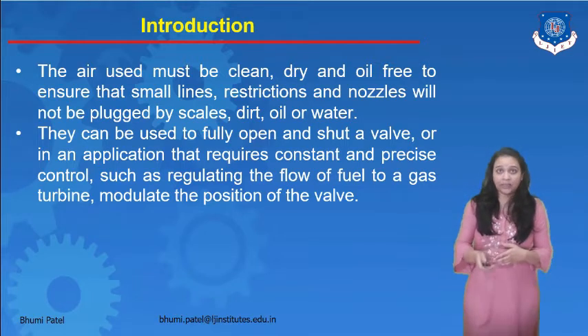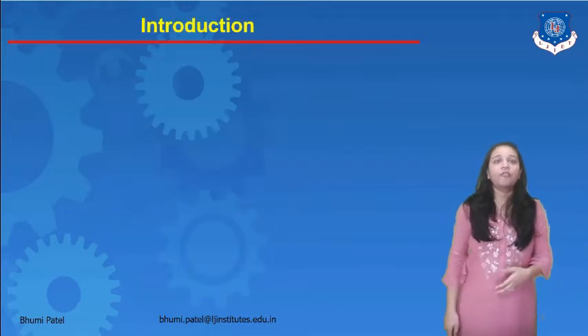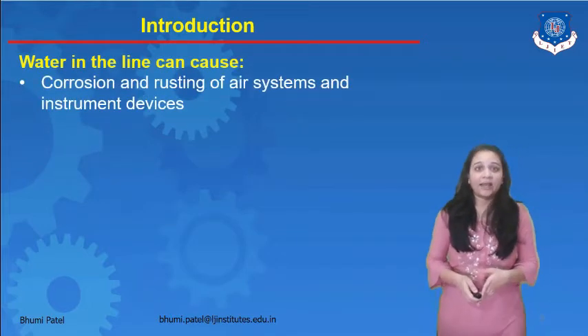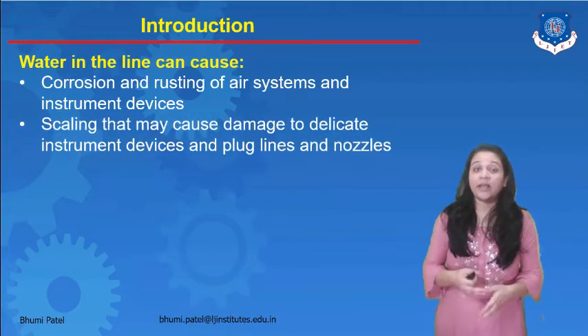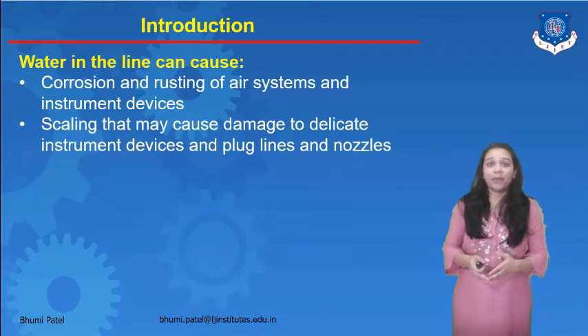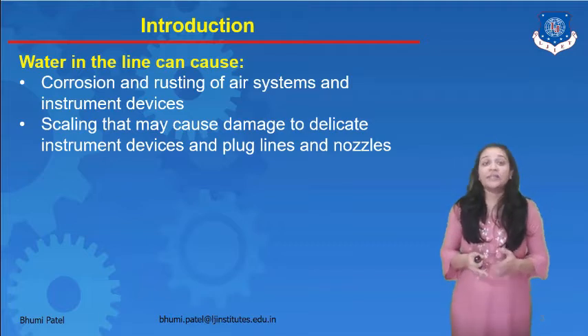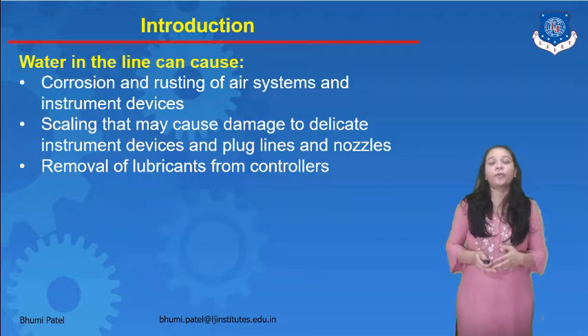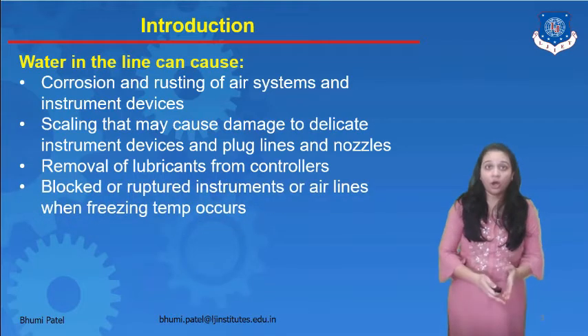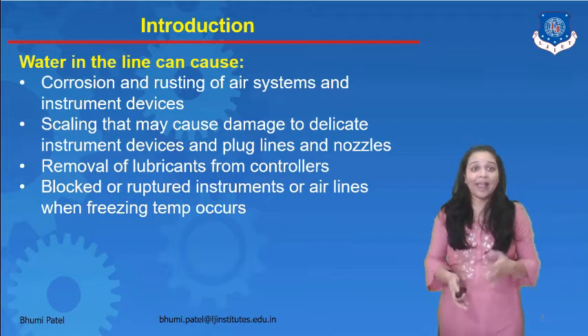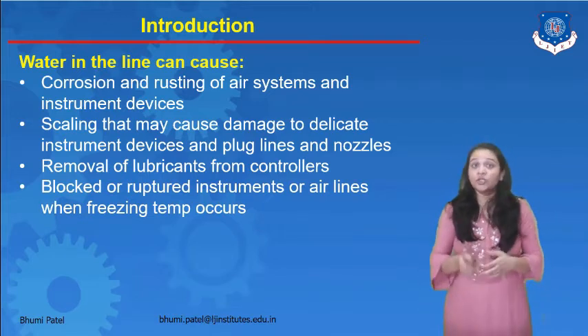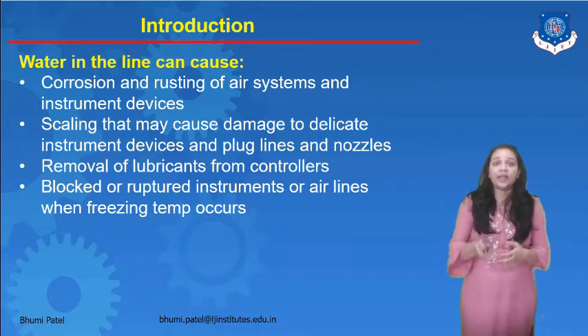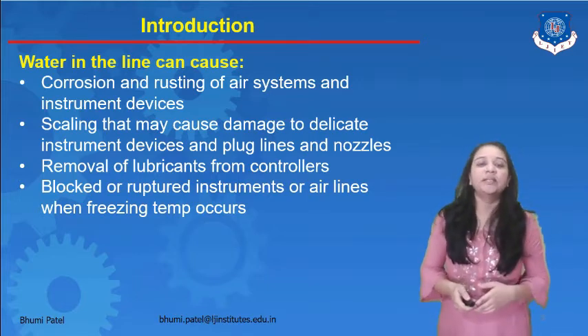The air must be clean, dry, and oil-free. Water in the line can cause corrosion and rust in the air system and instrument devices. Scaling may cause damage to delicate instrument devices and plug lines and nozzles. Removal of the lubricator from the controller, and water can block or rupture the instrument or air lines when freezing temperatures occur. Whenever water is present in the system, we have multiple problems.